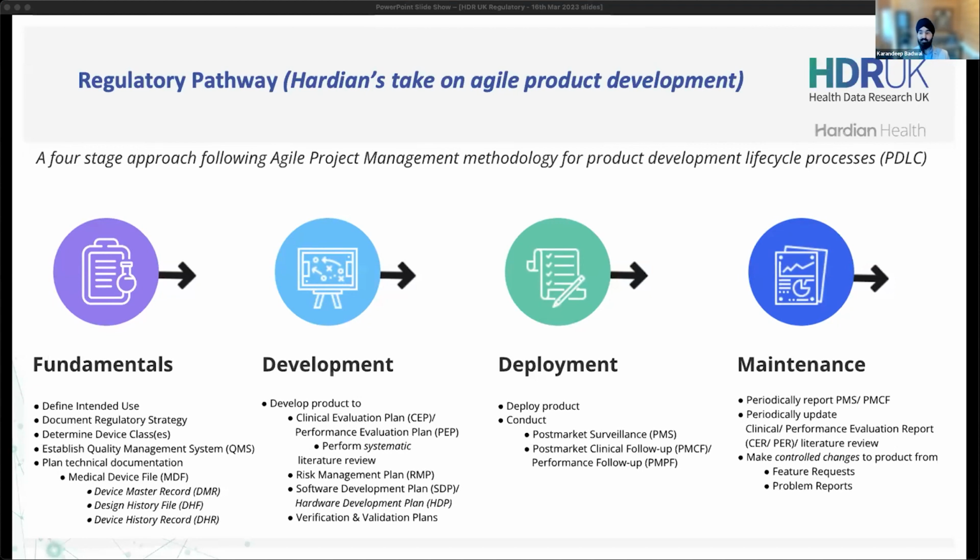Do you want to go for UKCA? Do you want to go for CE marking? Do you want to go to the US market? A lot of companies make the mistake, especially with the EU MDR situation, of saying, you know what, if we go down the US 510(k) route, we can get onto the market in 6 months. That very well might be true, but have you looked at it from a health economics point of view? Don't go for what is easiest, but go to the market where you're going to have the most impact. That's the most important thing here.